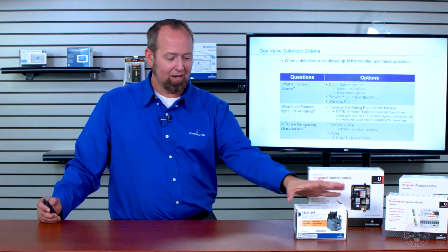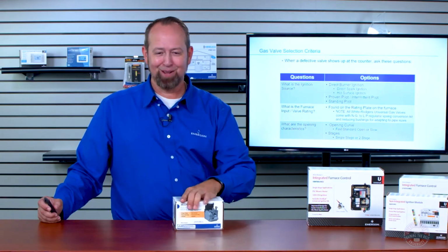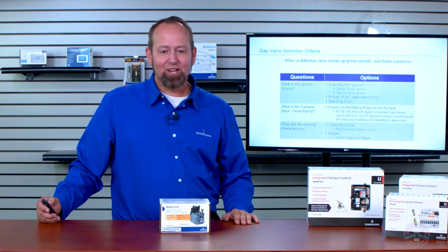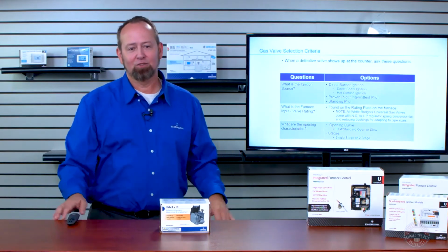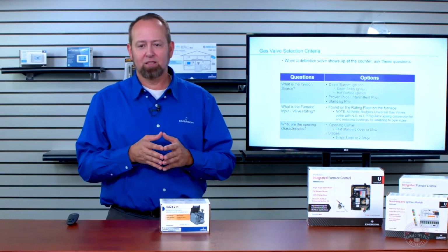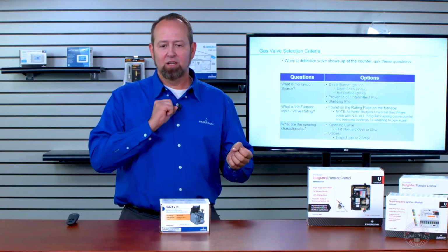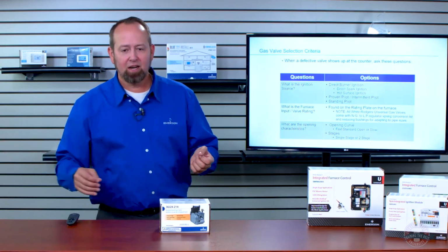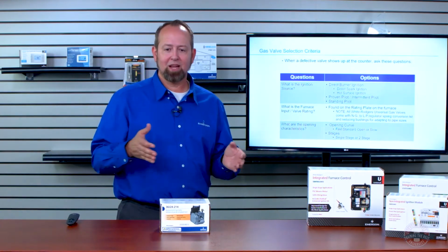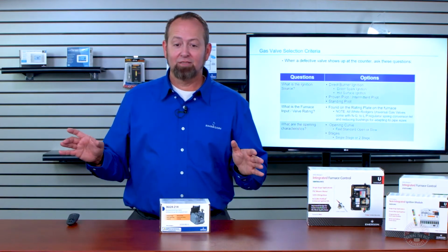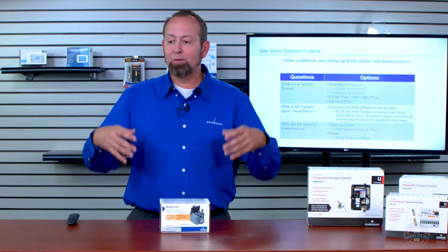And then I have a valve here I'm starting to grab already, and I will show it to you here in a minute. The opening curve is the final characteristic. And there are some gas valves that as soon as they're energized, you got the full amount of gas coming out immediately. Others, you may have a little bit of delay. Others are very slow, and the gas slowly builds up to pressure.